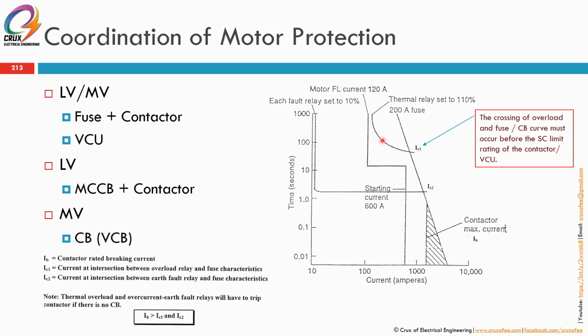And this is the overload characteristic or the IDMT. This is the fuse, or can be replaced with the circuit breaker lah, MCCB or VCB or similar lah. So for LV and MV, we can use the combination type fuse plus contactor lah. For the MV is the same, but they call it the vacuum contactor unit. For LV, we can also use the MCCB plus contactor with a fault protection. While for large MV motors, where the motor current is more than, for example, 400 amps or almost 400 amps, you need to use a circuit breaker lah, together with overload and also high set protection lah.